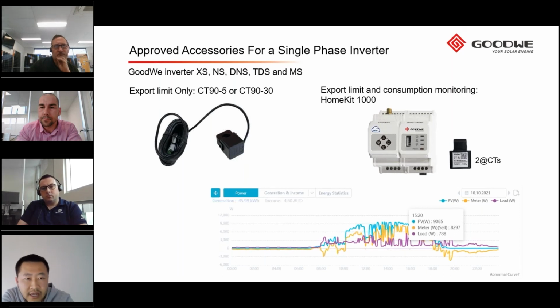And of course, if the customer has an export limit function request plus consumption monitoring, which is a very popular demand in the market, then you can just purchase this HomeKit 1000. This meter comes with two CT clamps. So by using this, the customer can do consumption monitoring. Basically, on the monitoring portal, besides the solar power generation curve, the customer can also see the load and consumption curve on the same platform. So that's for single phase.